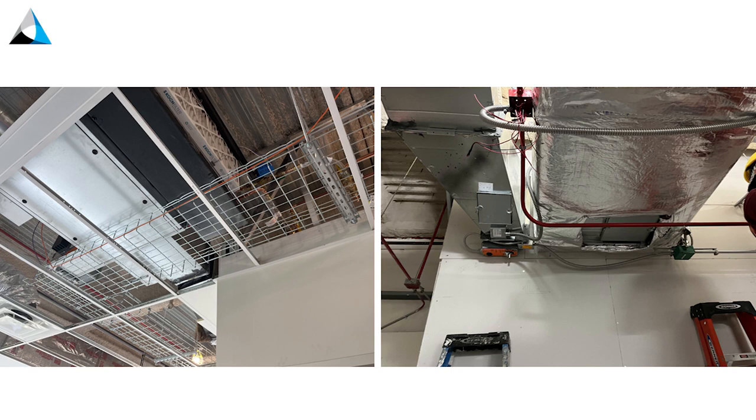This next video shows a lot going on at the same time, pulled from one of the case studies. We're already on emergency power, so you'll see about half the lights on. I'm in the middle of nurse call testing and fire alarm testing simultaneously — a lot of noises going on. You can see about half the lights are on — just the life safety lights. There has been a fire emergency reported in the building. The pressure monitor is still working, the door is open so it's red, the nurse call is still working. There's a lot of things going on at one time — it can get a little chaotic, but if it was easy, anybody could do it.